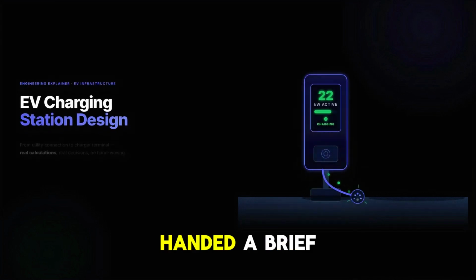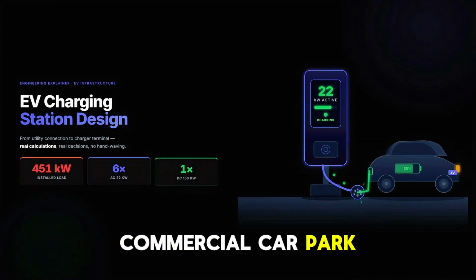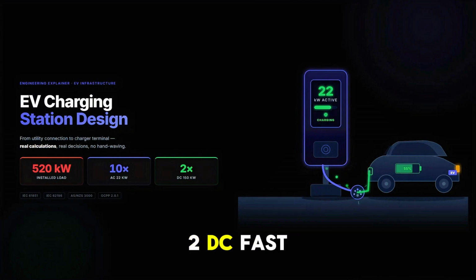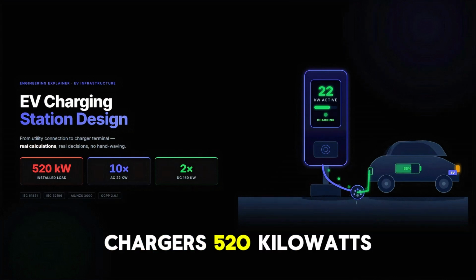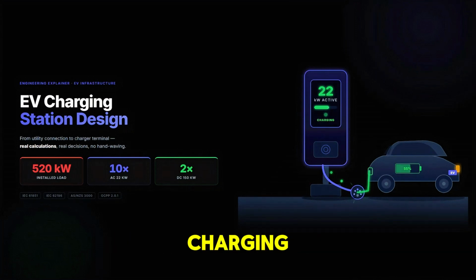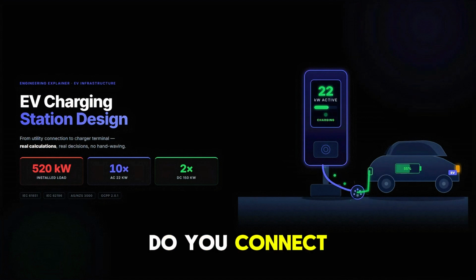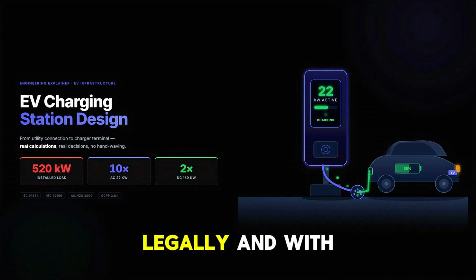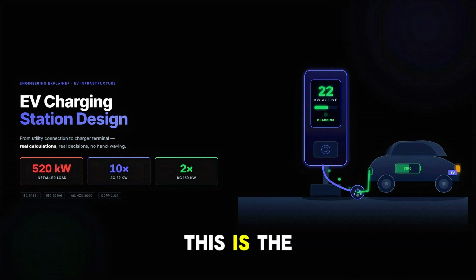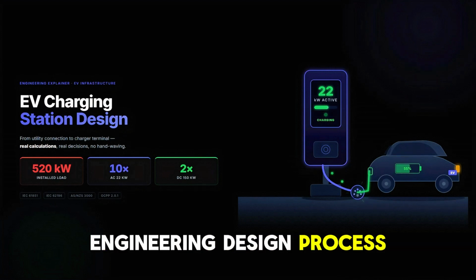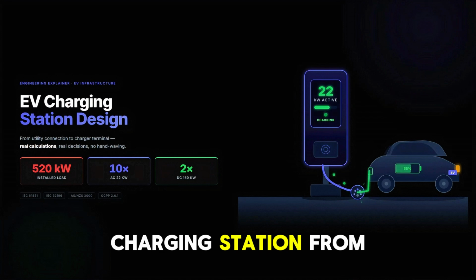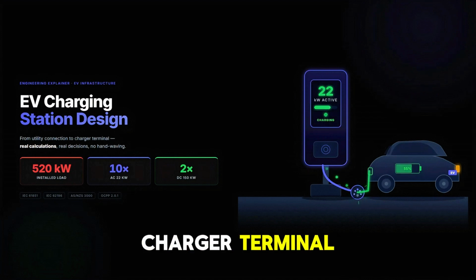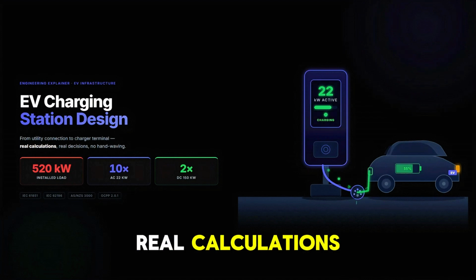You've just been handed a brief: commercial car park. 10 AC chargers, 2 DC fast chargers, 520 kilowatts of installed EV charging load. One question: how do you connect all of that to the grid safely, legally, and with room to grow? This is the step-by-step engineering design process for an EV charging station, from utility connection to charger terminal. No hand-waving, real calculations, real decisions.